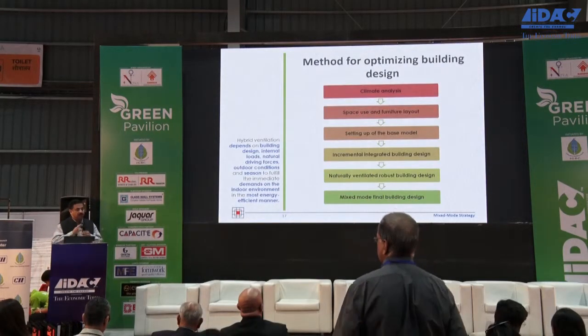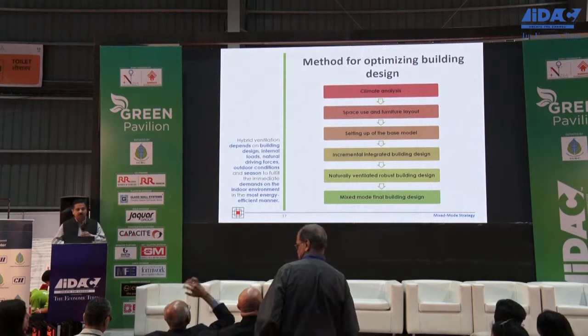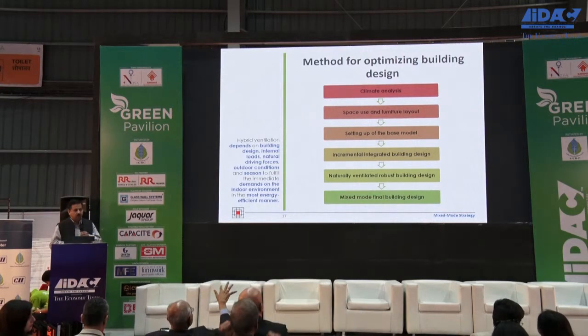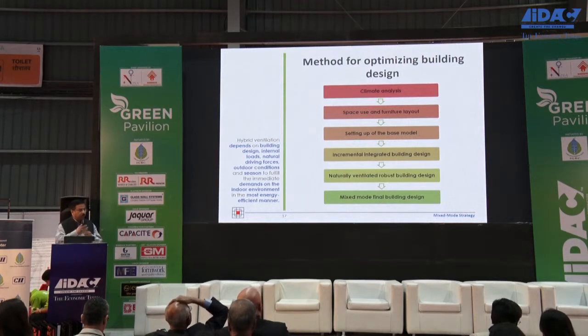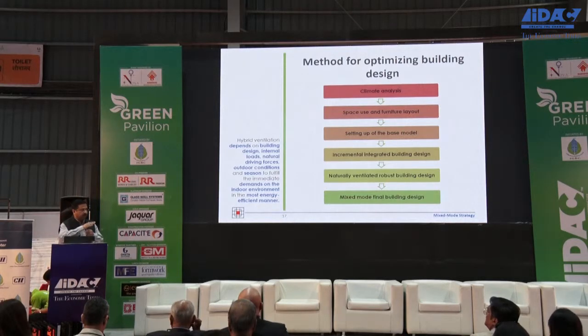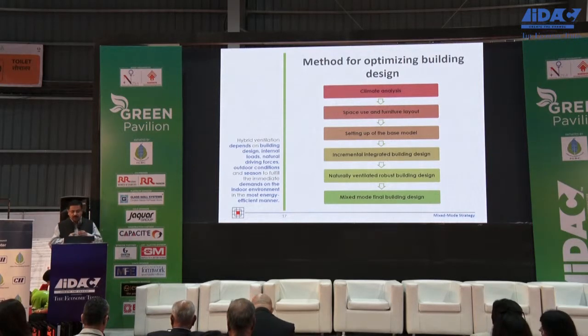Now, to conclude, I'll just give you a simple methodology for doing this kind of thing. The fundamental is to do a climate analysis. You need to know the space use and the furniture layout. Then set up the right base model, which is a mix in terms of the mixed mode strategy for the quantum of natural ventilation and the active systems using an HVAC system. Then comes incremental and integrated building design. The approach has to be comprehensive and holistic, where you use to full efficiency the passive side and the active side of the building, optimizing the total energy demand of the building as a whole.